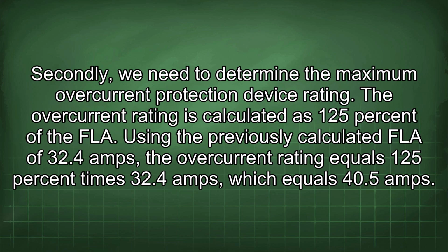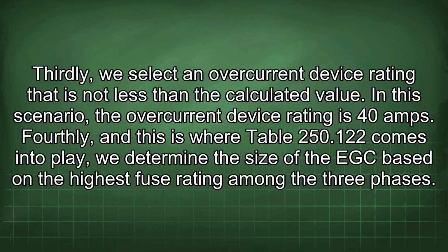Secondly, we need to determine the maximum overcurrent protection device rating. The overcurrent rating is calculated as 125% of the FLA. Using the previously calculated FLA of 32.4 amps, the overcurrent rating equals 125% times 32.4 amps, which equals 40.5 amps. Thirdly, we select an overcurrent device rating that is not less than the calculated value. In this scenario, the overcurrent device rating is 40 amps.